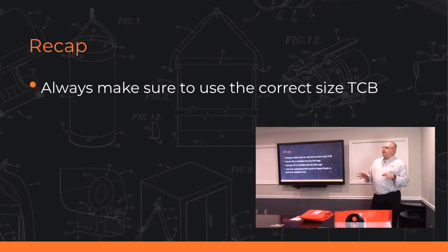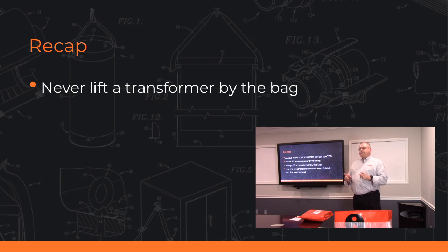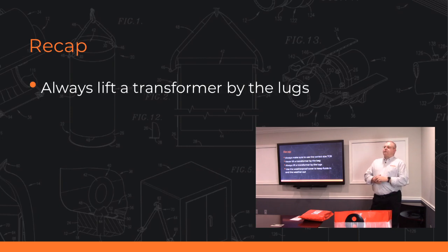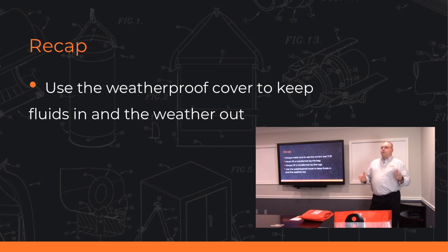Remember, when you're using the TCB, always make sure you are using the correct size TCB. Never lift a transformer by a bag. Always use your approved lifting sling and lift it by the transformer manufacturer's lifting lugs. Use the weatherproof duffel to keep transformer fluids in and the weather out.